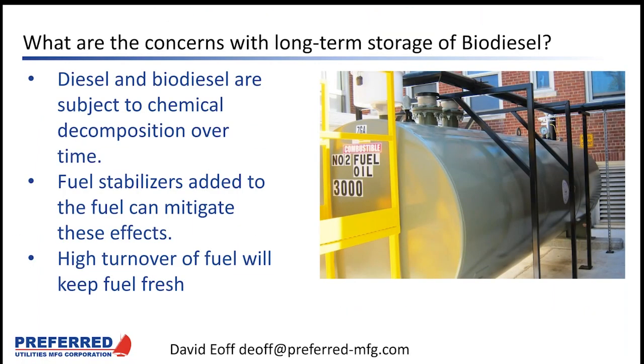Finally, let's talk about the long-term concerns of storing biodiesel. To start with, it's important to understand that both diesel and biodiesel are subject to chemical decomposition over time. This is an oxidation reaction that begins as soon as the fuel is refined. A lot of facilities will burn and replace their fuel fast enough to keep it fresh, so chemical decomposition is not a problem for them. Adding a fuel stabilizer can greatly slow fuel degradation and extend the life of the fuel. Preferred and our representatives offer fuel stabilizers, and they can be added to our fuel polishers.